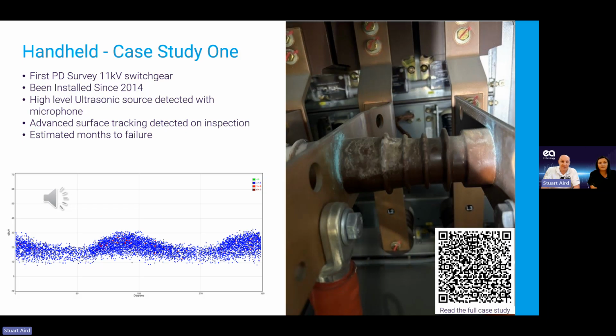And you look at that picture, we must be looking at months at the most that could have carried on discharging like that. And we have in the past seen monitoring cases where we've actually monitored something from not detectable to failure within sort of 3-4 months. So the fact that we've done this PD survey and we've picked it up on this occasion is maybe partly lucky rather than well planned as such.